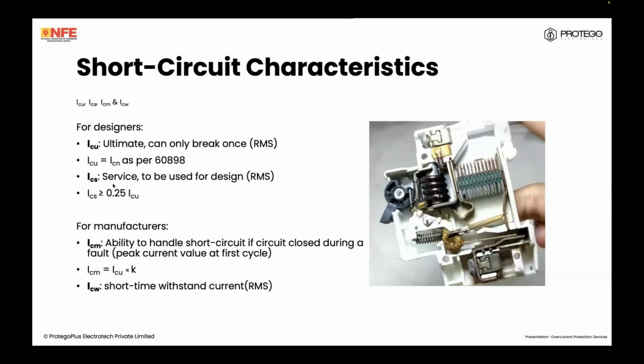checklist. So for design, we use something called ICS, which is the in-service breaking capacity. These are all root mean square values of current. This is what value of short circuit the OCPD can disconnect constantly under design. For a fuse, obviously, once it blows, so it's not valid. Generally speaking, the standards require this in-service breaking capacity to be at least 0.25 of the ICU, the ultimate capacity. So I've got an MCCB here, and for instance, for 415 volts, it happens that the ICU is the same as the ICS. Because it has to be greater than or equal to 0.25 ICU, ICS equal to ICU is perfectly adequate.